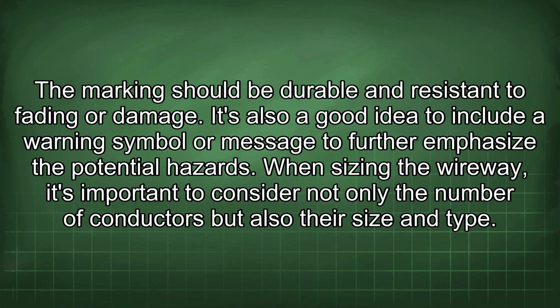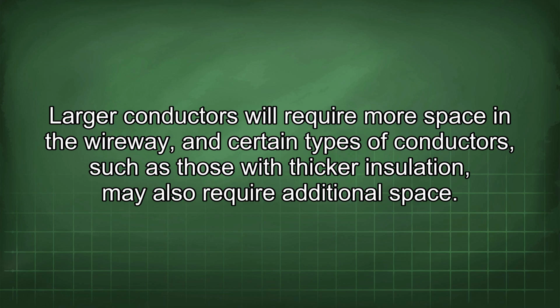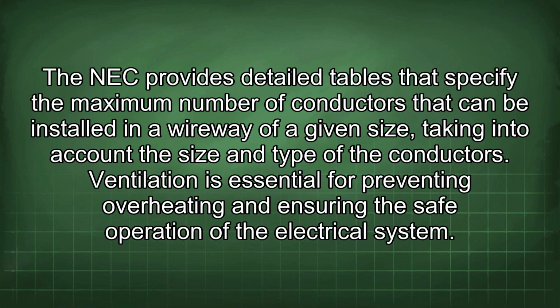When sizing the wireway, it's important to consider not only the number of conductors but also their size and type. Larger conductors will require more space in the wireway, and certain types of conductors, such as those with thicker insulation, may also require additional space. The NEC provides detailed tables that specify the maximum number of conductors that can be installed in a wireway of a given size, taking into account the size and type of the conductors.